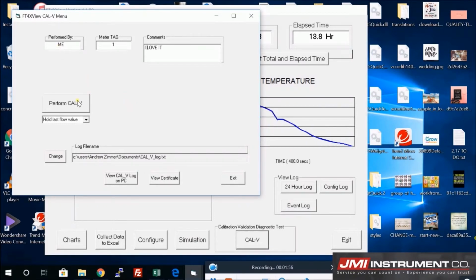So now I'm going to tap Perform Cal-V. While this is running under pipe conditions, I wanted to talk about your alternative to this very simple software. A lot of competitors claim that they can do a calibration validation, which compares you to the NIST traceable standard. But many of them need a voltmeter. You have to go and find a paper certificate that was given to you when you purchased the meter, go into jumper settings, generate voltages, and hit certain points of a calibration.